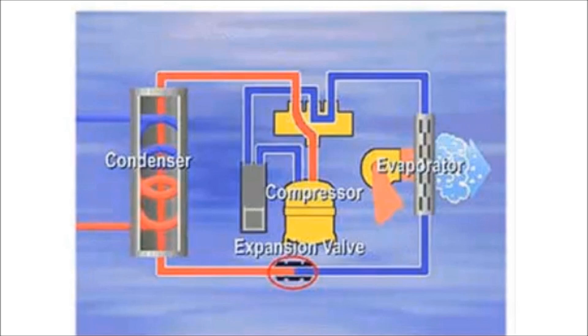The new, cooler, drier air is circulated back into the room with a blower fan. The refrigerant moves into the compressor, which is a pump that raises the pressure so it will move through the system. The increased pressure from the compressor causes the refrigerant to heat to roughly 120 to 140 degrees.